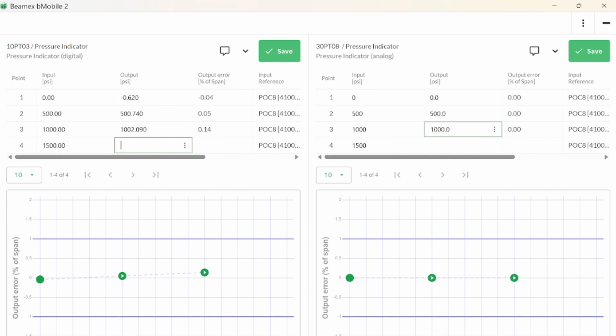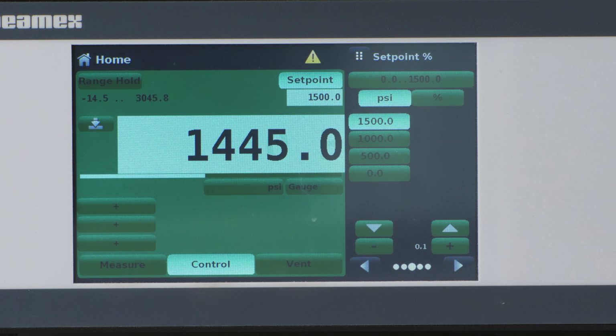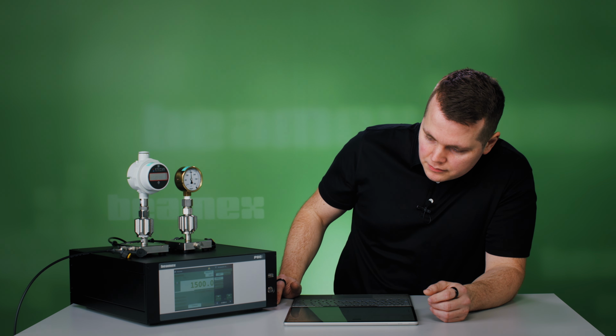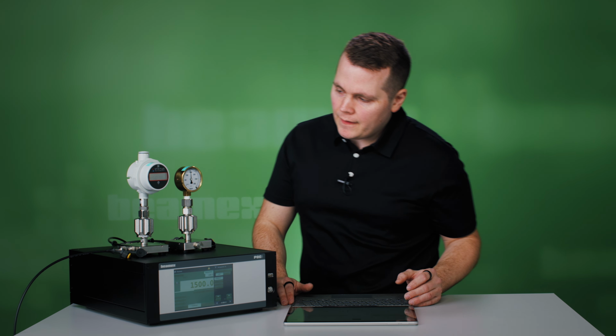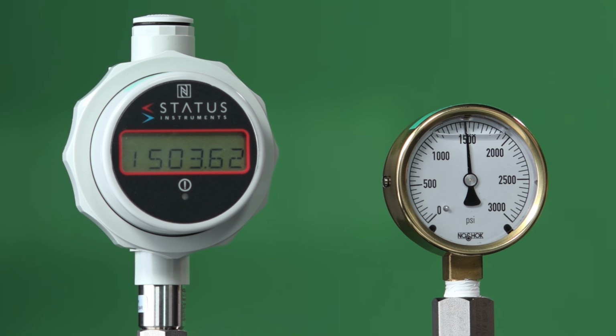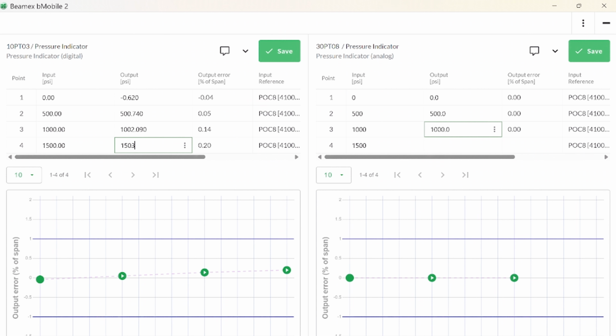There we go. And now onto the last calibration point. There we go, 1500 psi. And on the digital, it reads 1503.62. The analog one reads 1500. There we go. Now that we've got the calibration points recorded in the table mode, I can click on save.